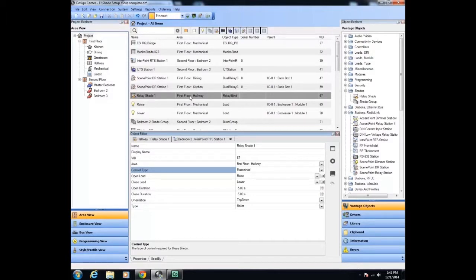It is that shades appear within the shade widget only within groups. Any shade not included in at least one shade group will not be exposed for control within the widget. And if there are no shade groups created, the widget will not be made available within the Equinox environment. So, with the grouping requirement in mind, let's discuss the idea of groups.